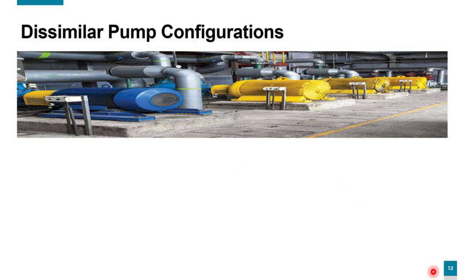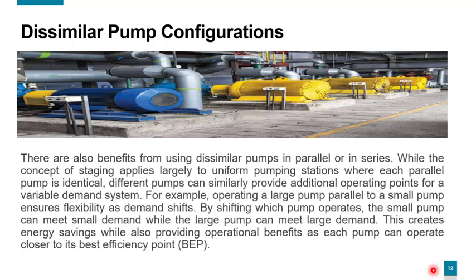Dissimilar pump configuration, which we saw a while ago in the curve: there are also benefits from using dissimilar pumps in parallel or series. While the concept of staging applies largely to uniform pumping stations where each parallel pump is identical, different pumps can similarly provide additional operating points for a variable demand system. For example, operating a large pump parallel to a small pump ensures flexibility as demand shifts. By shifting which pump operates, the small pump can meet small demand while the large pump can meet large demand, as we see in the curve. This creates energy savings while also providing operational benefits, as each pump can operate closer to its best efficiency point.